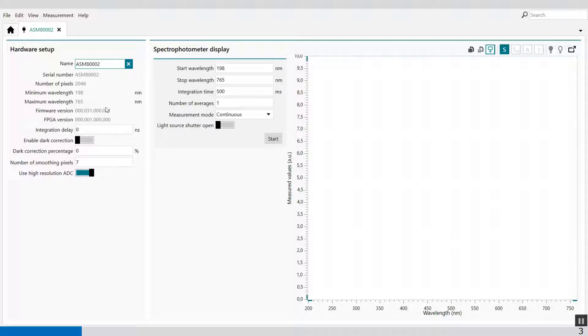Then we have the dark correction percentage — an input field which can be used to specify the percentile value of the dark correction from 0 to 100%. The weight of the black pixels subtracted from the raw data can be set using this property. When this value is set to 0%, no correction is performed. When this value is set to 100%, the value of the black pixels is completely subtracted from the measured data.